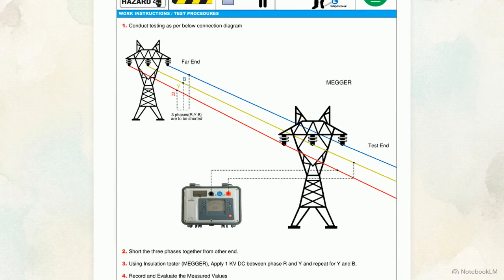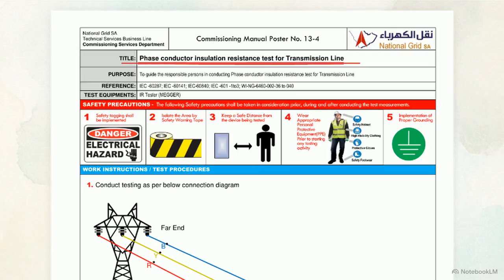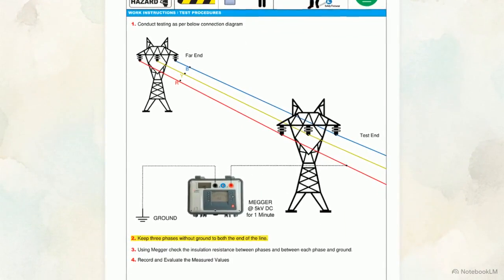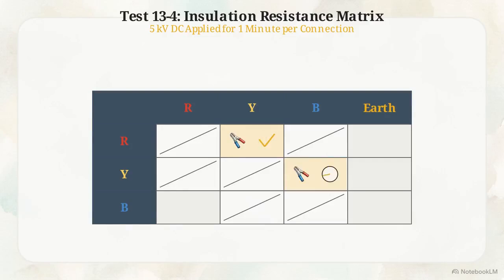witnessed before normalization. This diagram shows test 13-4, evaluating phase conductor insulation resistance. For this procedure, all 3 phases must remain totally isolated from ground at both ends of the transmission line. Technicians apply 5 kV DC for 1 minute, checking phase-to-phase insulation across RY, YB, and BR, followed by phase-to-earth resistance.